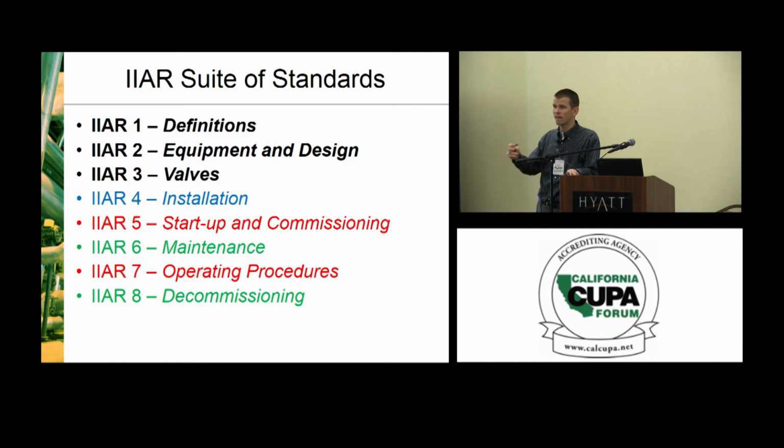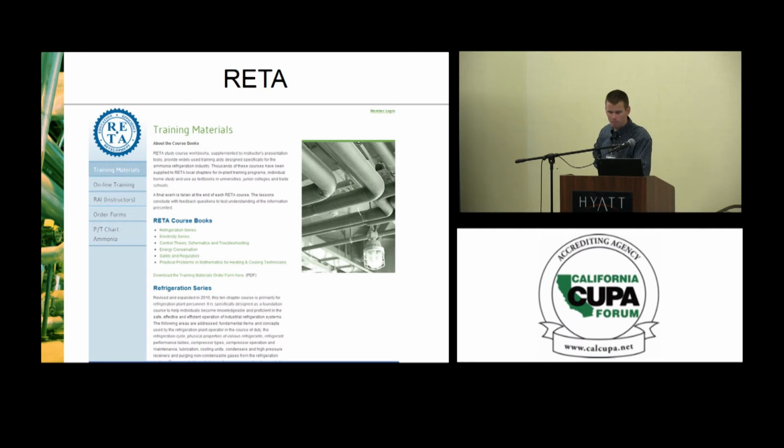There are things you can do, like if you're concerned, you can do testing. You can do ultrasonic testing. So if you know it's carbon steel, you can test it and determine a thickness. But in the absence of the original design specs, the original thicknesses and so forth, it's still kind of an estimation. So I don't know what else to say about that one.